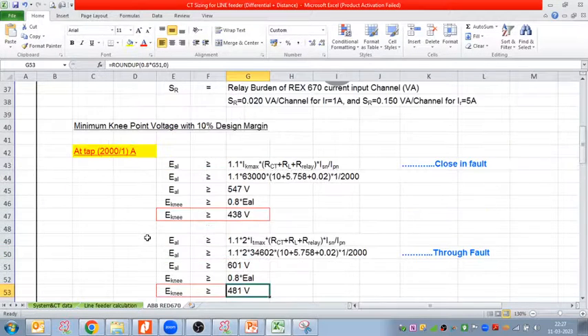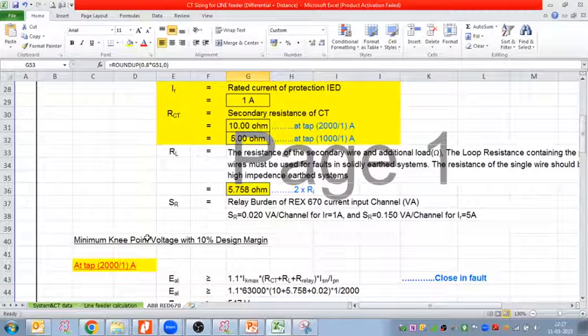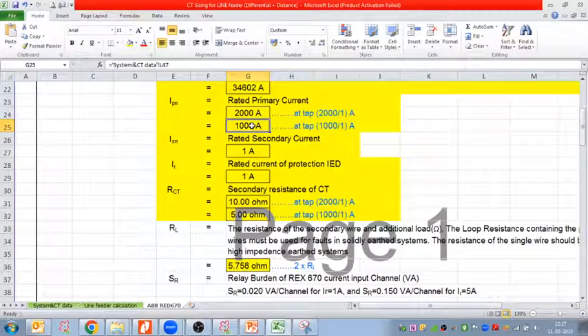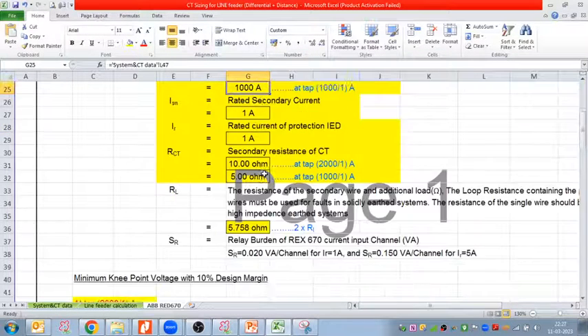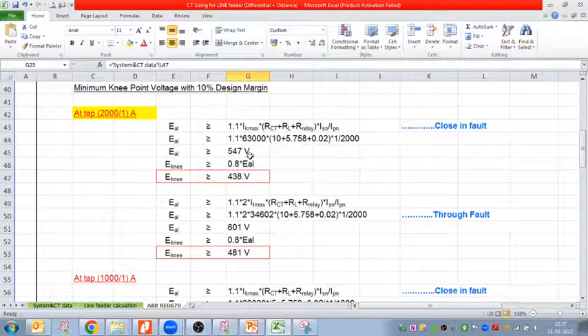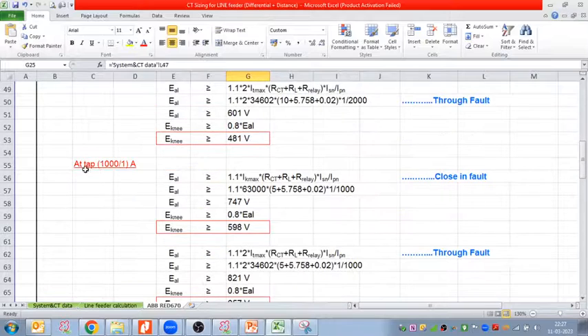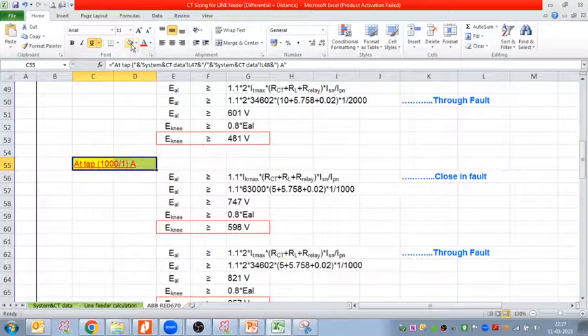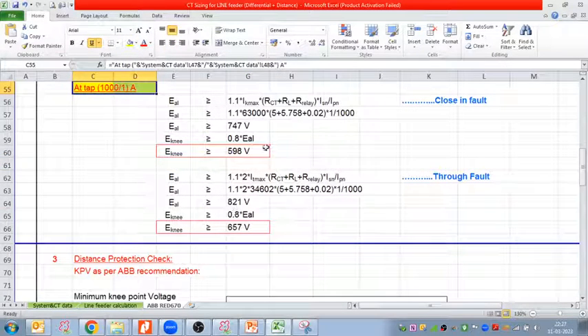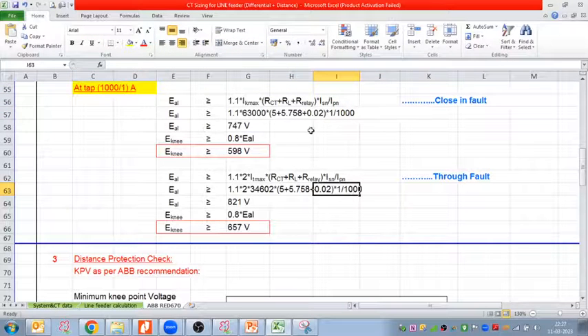Now, since we have two tappings, two ratios we are using, we can do the same calculation for the other tap, which is 1000 ampere. Same formula only. What is going to change is the current: initially we were dividing by 2000, and now in this case we will divide by 1000 only. So at tap 1000 by 1, 1000 by 1. So 1000, now 1000 here.